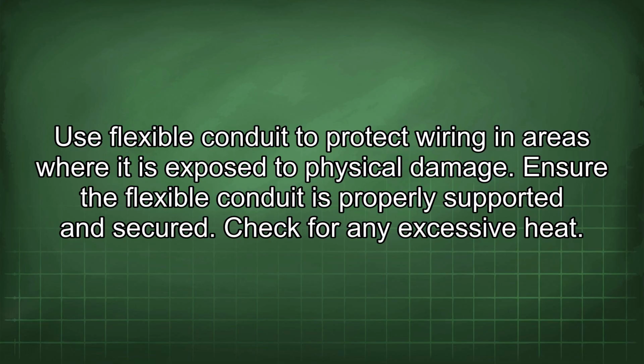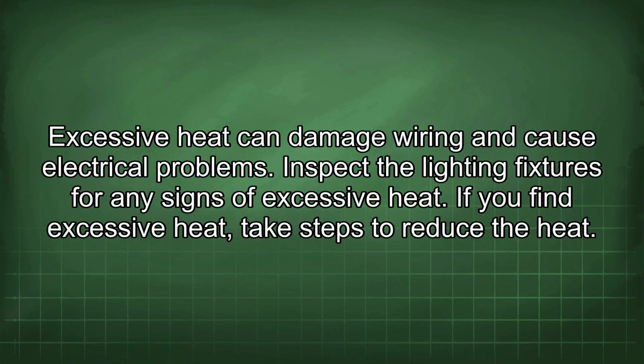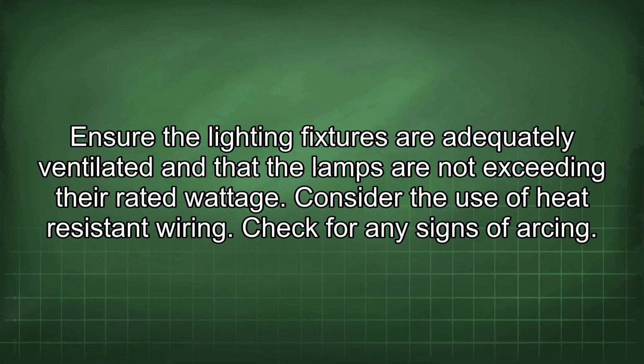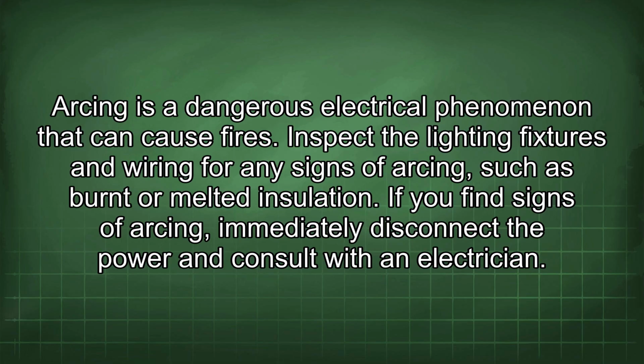Check for any excessive heat. Excessive heat can damage wiring and cause electrical problems. Inspect the lighting fixtures for any signs of excessive heat. If you find excessive heat, take steps to reduce the heat. Ensure the lighting fixtures are adequately ventilated and that the lamps are not exceeding their rated wattage. Consider the use of heat-resistant wiring. Check for any signs of arcing. Arcing is a dangerous electrical phenomenon that can cause fires.